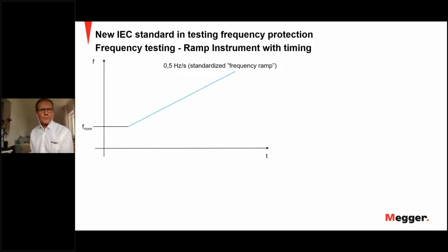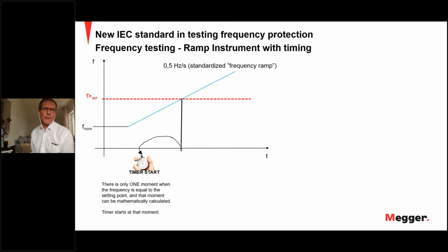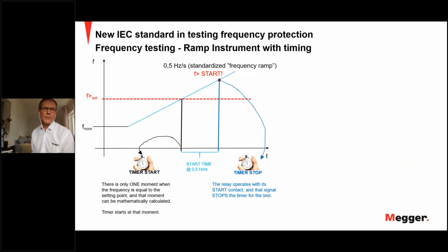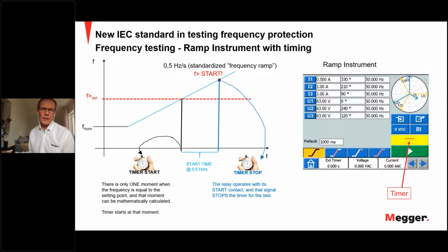So when you test over frequency protections, for example, you can do that in the ramp instrument, which has timing in SVERKER 900. You shall not do it with a pre-fault fault instrument, because this is not really according to the standard to simulate the right changes of frequency. So you use the ramp and you ramp the frequency, increase it, and the timer starts, and the relay operates, you get the trip and you get the time. And that is very simple to create with SVERKER 900, because in the ramp instrument you also have the timer to do the measurement of this.